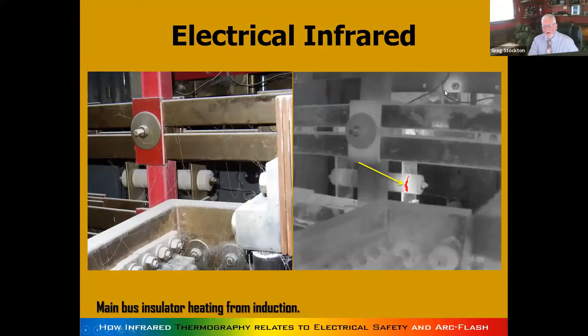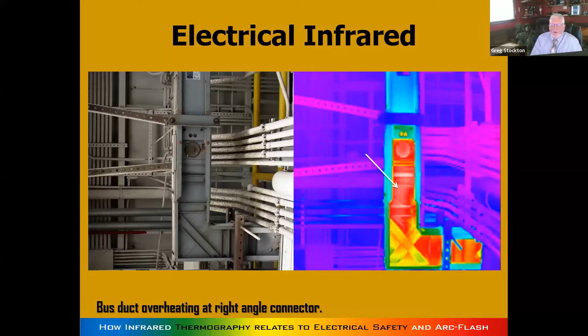Bus ducts were one of the first uses for infrared thermography, because manufacturers selling bus ducts couldn't convince the chief electrical engineer at the plant that they had enough space between all that power and that it wasn't going to explode. So they kind of used it as a sales tool.